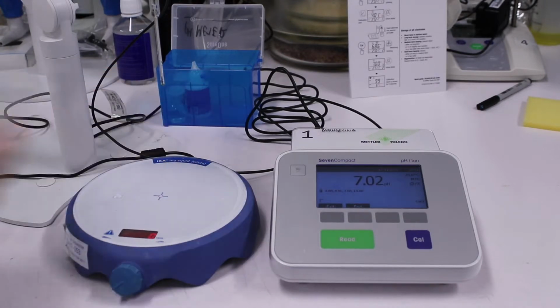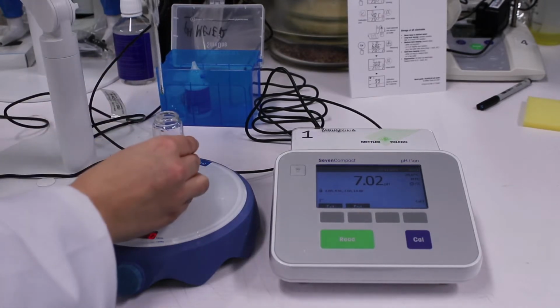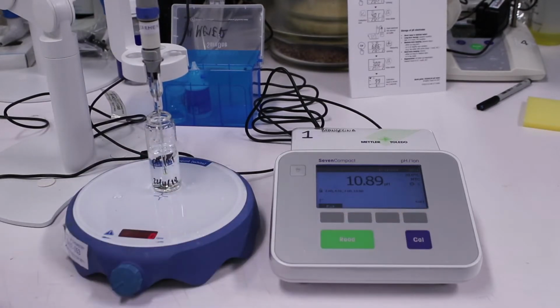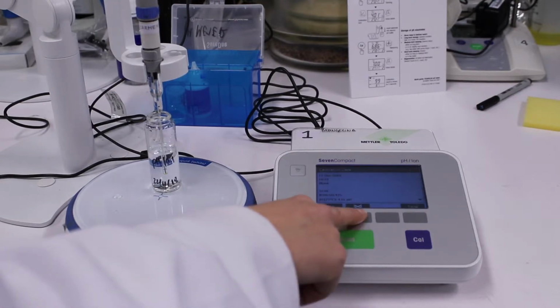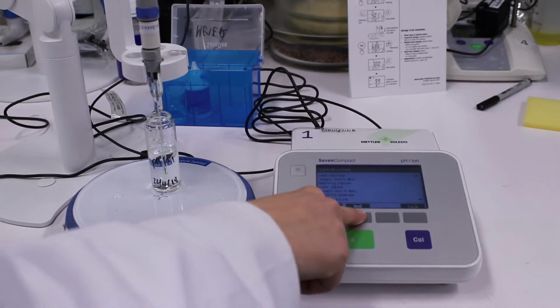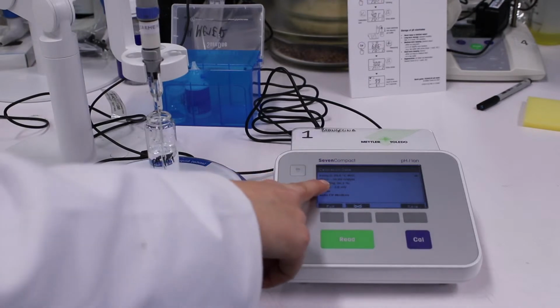tap it, and put it into the third solution. Press Cal again, and now it should read Cal 3. Once you've got all 3 readings, press End, and then press the same button twice. This is going to give you a calibration curve.